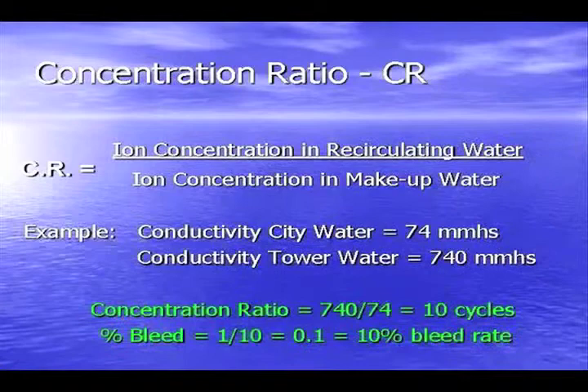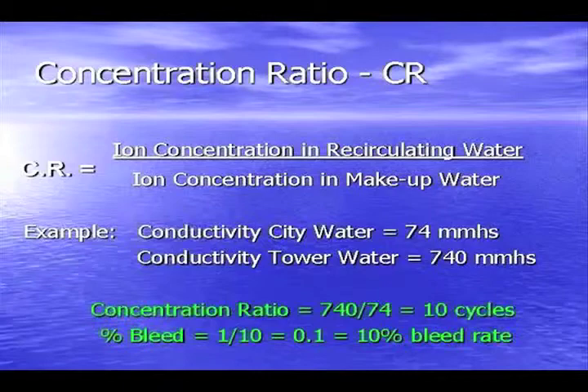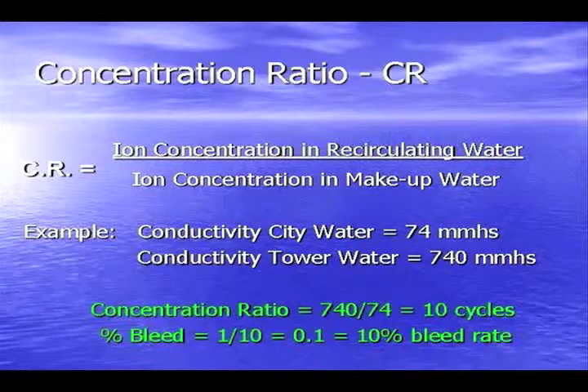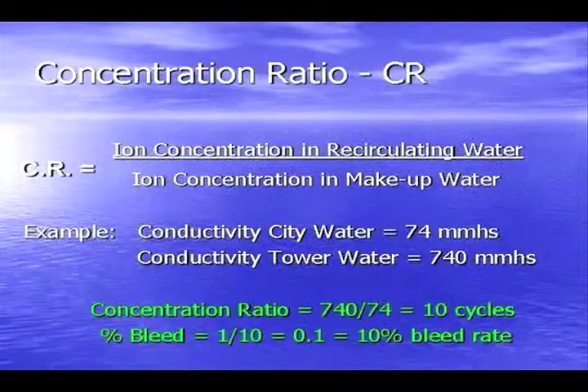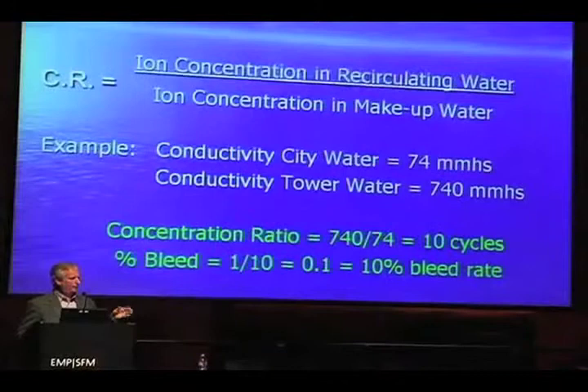The definition of concentration ratio is basically the ion concentration in the recirculating water divided by the ion concentration of the makeup water. That determines your cycles. For example, the conductivity of city water here is about 74 micromhos. If your tower runs at 740 micromhos, you're concentrating it up and running basically 10 cycles — 740 divided by 74 is 10 cycles. At 10 cycles, you're running about a 10% bleed rate, meaning about 10% of the water going to the cooling tower is being removed through bleed. The higher you go, the smaller percentage your bleed rate; the lower you go, the higher percentage your bleed rate.